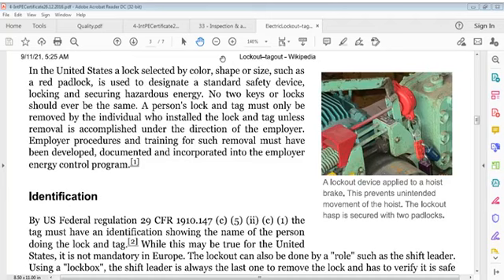No two keys or locks should ever be the same. A person's lock and tag must only be removed by the individual who installed the lock and tag, unless removal is accomplished under the direction of the employer. Employer procedures and training for such removal must have been developed, documented and incorporated into the employer's energy control program.